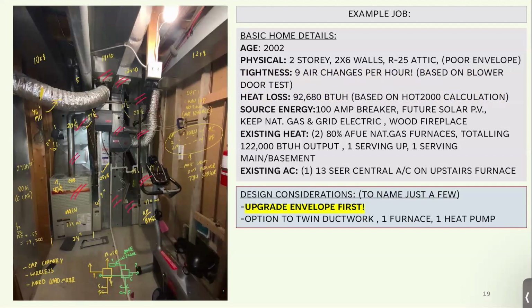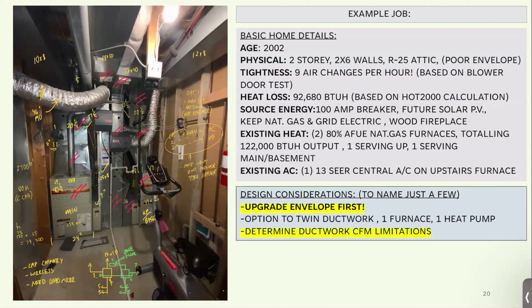We got through a lot of different iterations, had to do a lot of notes. It's a challenge. And the largest thing, and I'm sure Jordan's going to say the same thing, is that we need to understand the CFM limitations of your current ductwork. Otherwise, the heat pump will not work correctly, no matter which system you put in, fully electric or hybrid. And that's probably one of the biggest hurdles we have today, because ductwork is atrocious in some homes, to put it lightly. And it's the major cause for service-related issues.